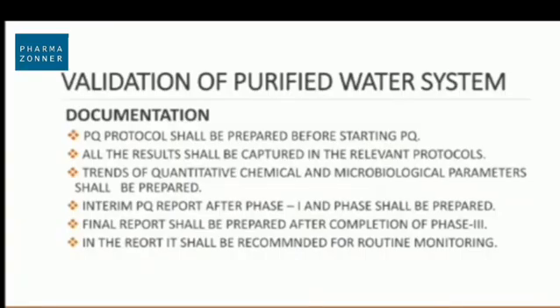Documentation required for performance qualification of the water system: a protocol must be prepared defining the general description, training records, specifications, and sampling frequencies. Results shall be captured in the relevant protocol. Trends of quantitative, chemical, and microbiological parameters shall be prepared after each phase. An interim report for Phase One and Phase Two shall be prepared so the system can be released for the next phase. Once Phase Three is completed, the final performance qualification report shall be prepared.